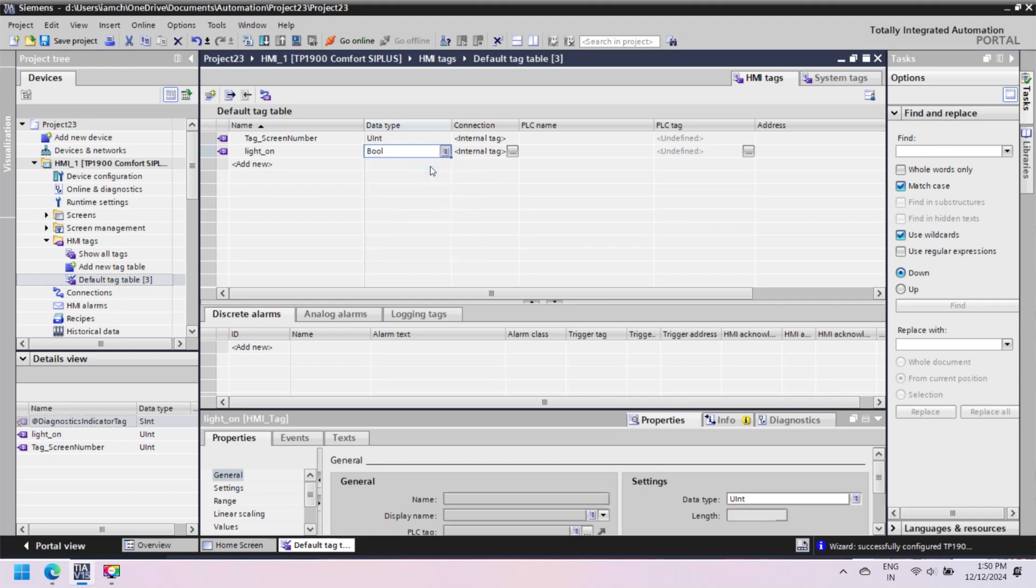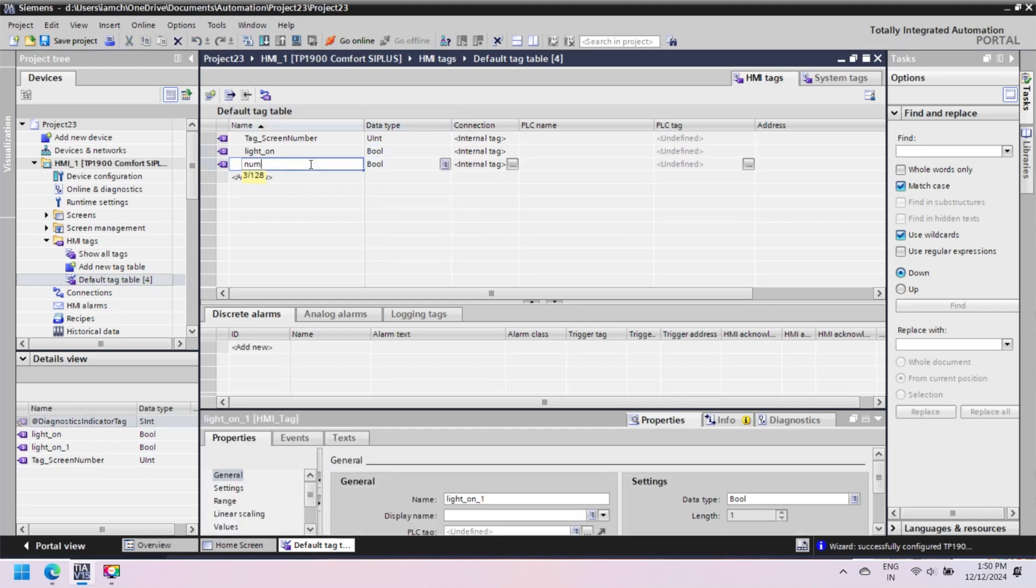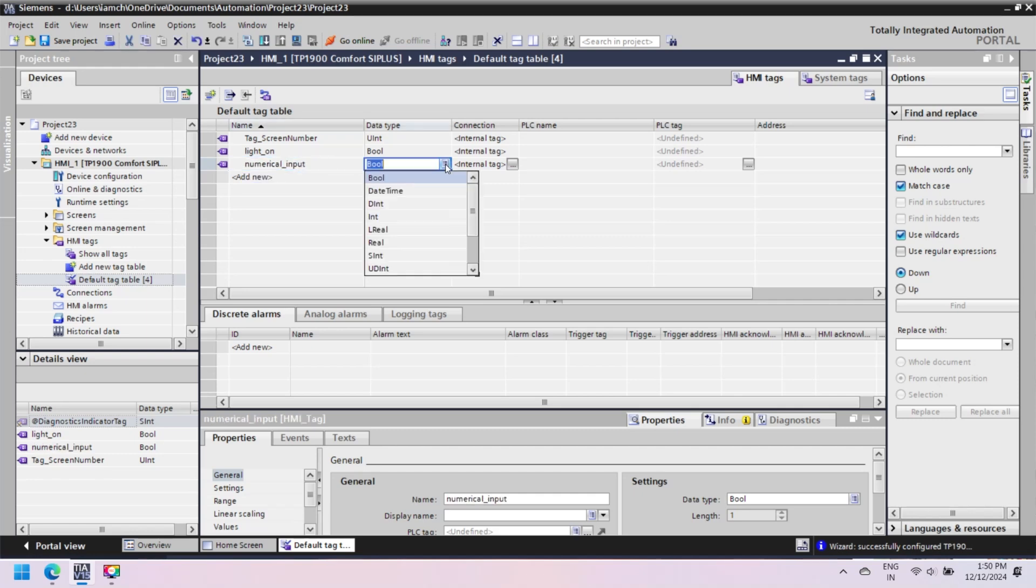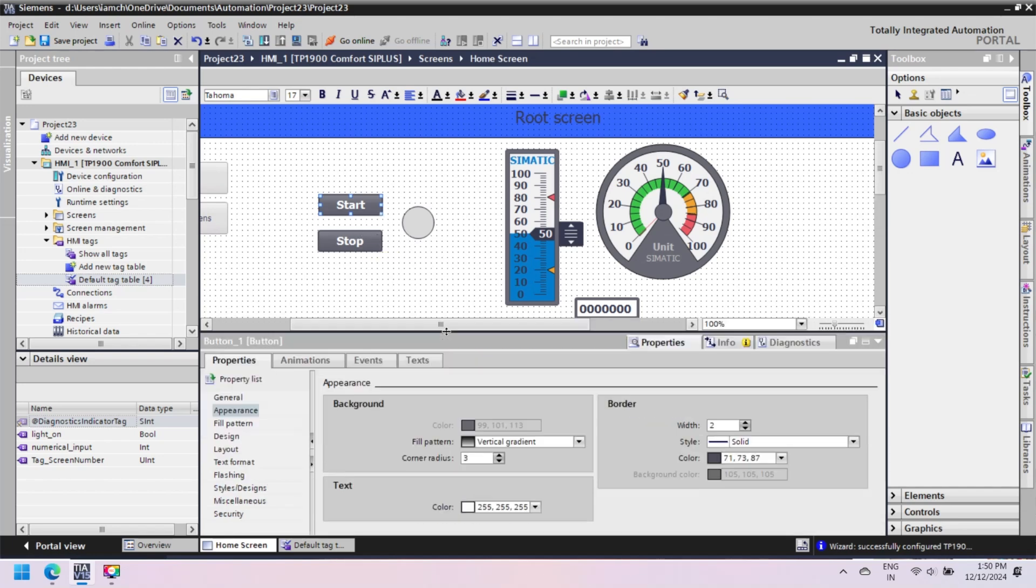These tag tables are available by default, or you can also add Tag Table. In Tag Table, insert Tag Name, select Tag Data Type like bool, int, string, etc. In Connection Column, select Internal Tag if you want these tags internally used for HMI, or otherwise select Connection if you want to browse PLC Tag.